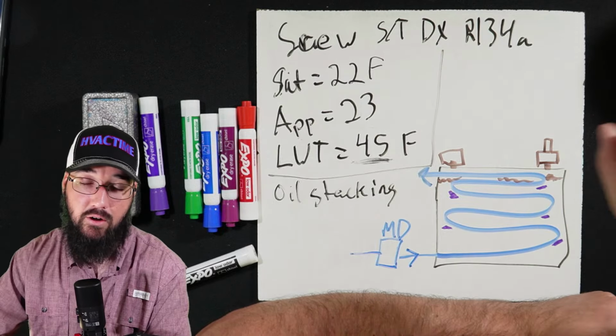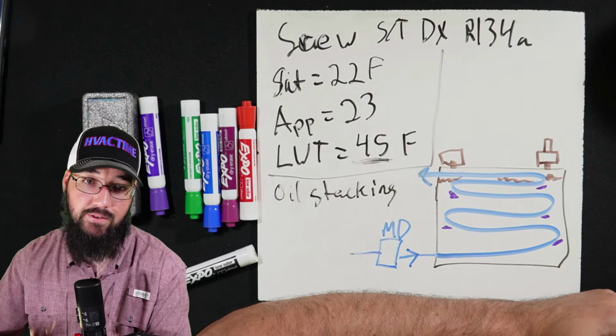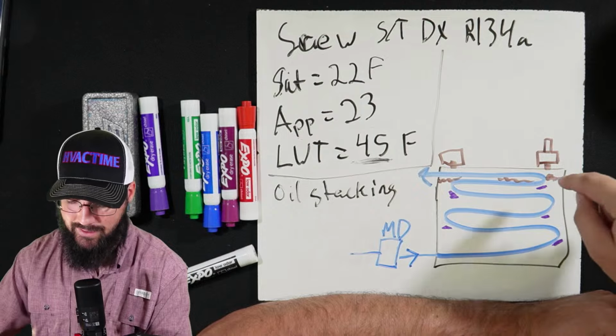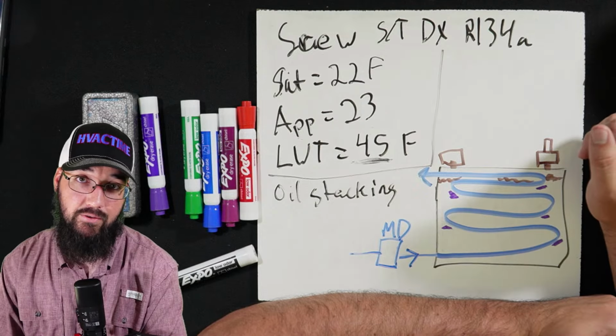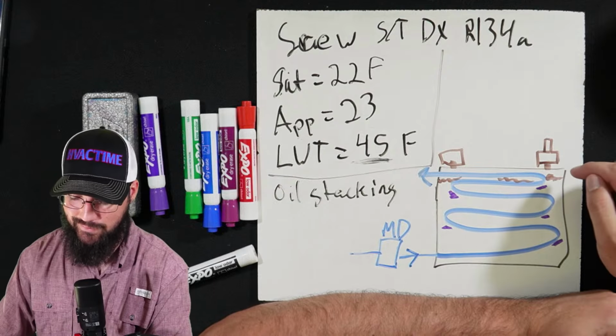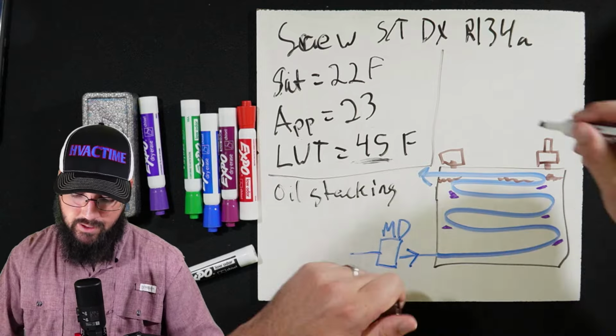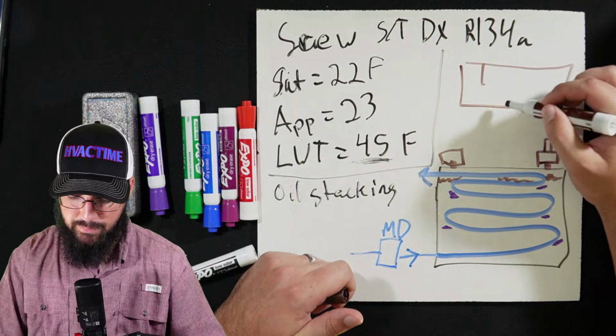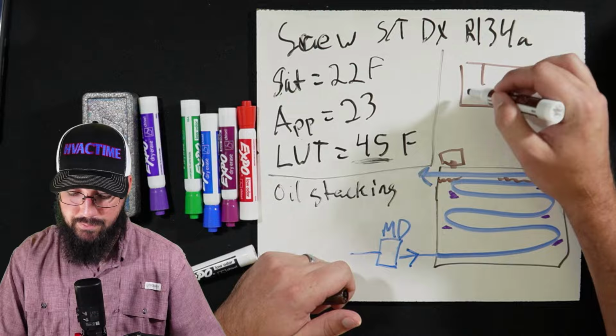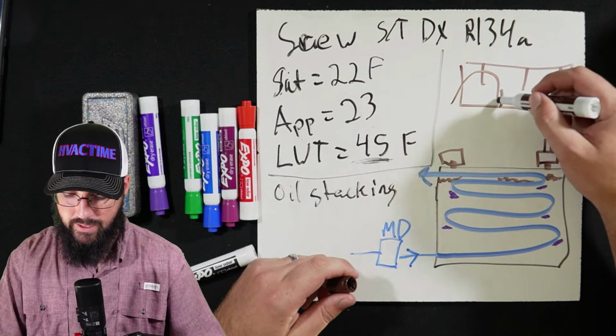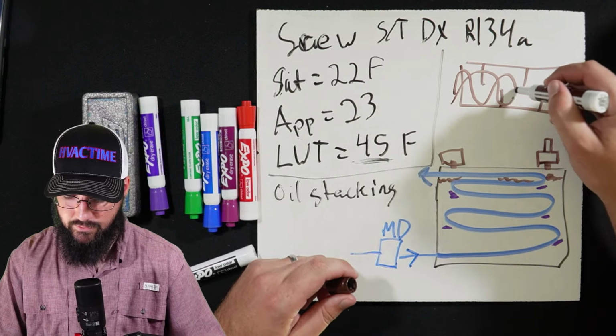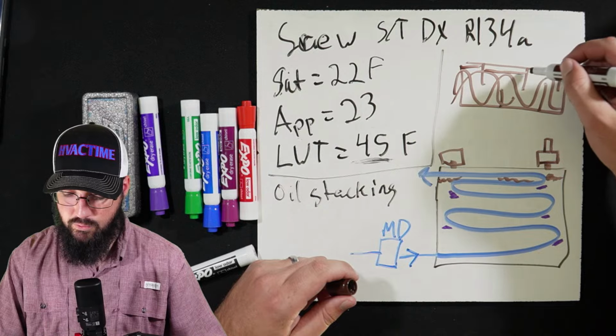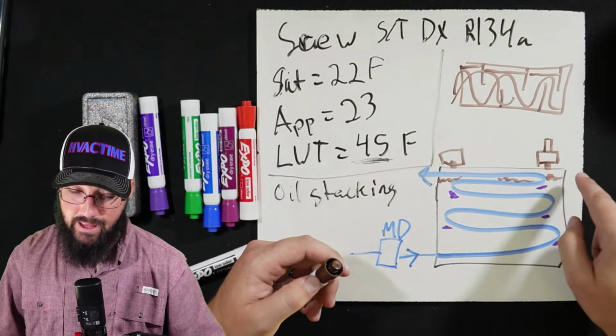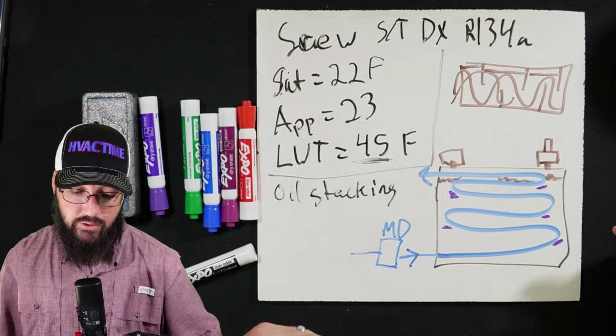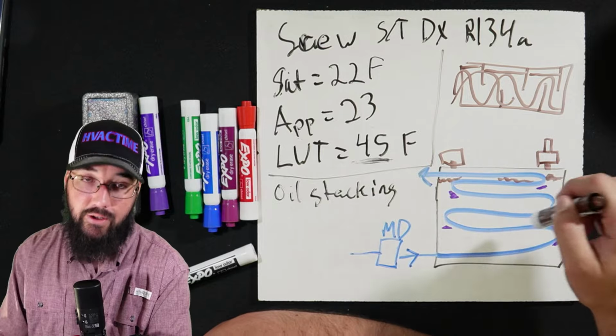Even if there's air bleeders close to the chiller, in the piping itself, right? Just because the piping has air bleeders in it, these evaporators make excellent air separators. I mean, they're amazing air separators, because of the baffling in here. So keep in mind, there's baffling inside of these evaporators that the water flow is going through. All of these little choke points up here create a perfect turbulent spot for that air to just stack in there, which is where having bleeders up on these ports can be really, really useful. So I'd highly recommend maybe looking into that.